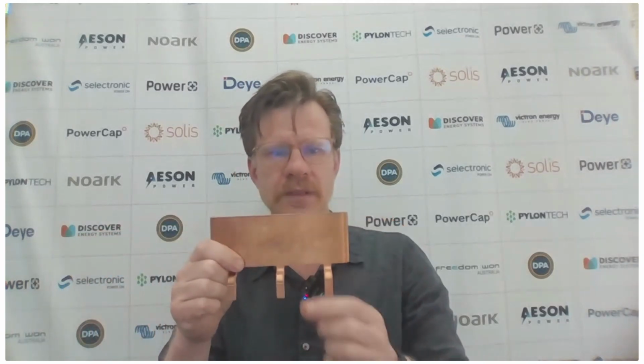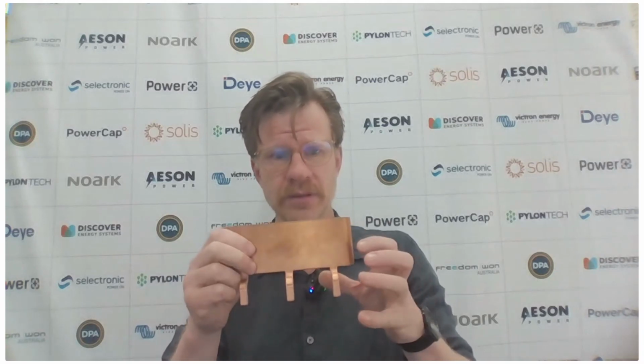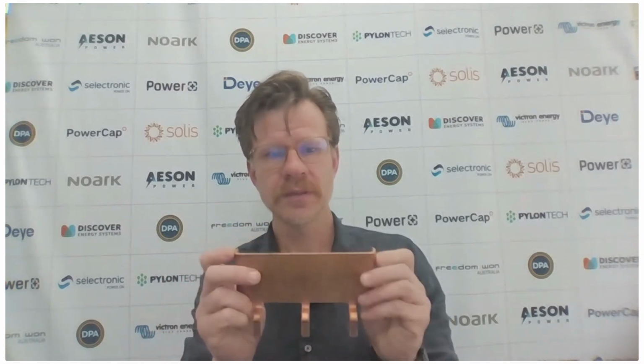While we're waiting, I'll show you this, and I'll show you it again at the end if I have time. This is a bus bar I've had made up for Helios batteries. You have a pair of these and 3 125 amp CBI breakers. You put 3 Helios together, because normally you won't need more than 125 amps, you won't even need that per battery if you're using up to a 10 kilowatt inverter. This allows you to mount 3 on a DIN rail with 2 of these bus bars and go off from the sides to your inverter. I've got a whole box made up with that, I'll show you at the end if I have time.